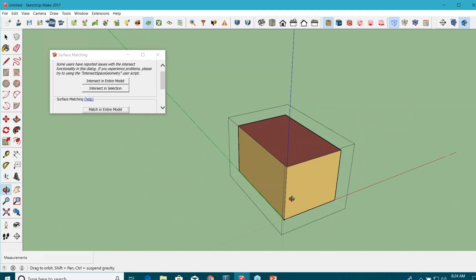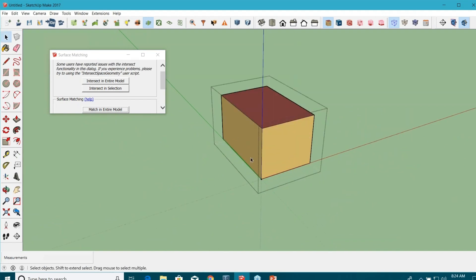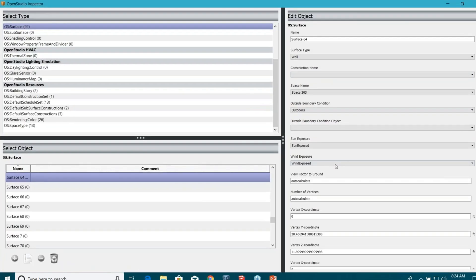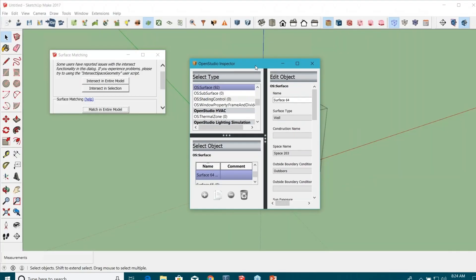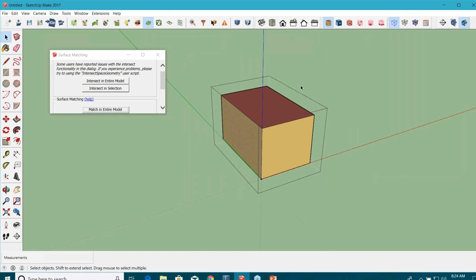You have to make those corrections manually. Either you can select each and every wall and change the properties in this inspector tool. For example, you can see this particular wall has outside boundary conditions. It has sun exposure, wind exposure. It means that when you run the simulation, they will act as outdoor boundaries and the thermodynamics that will happen through this surface will act as per that.